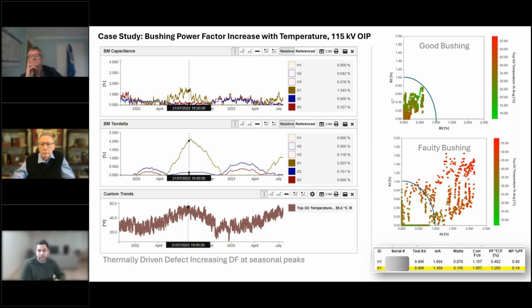Okay. The graphs on the right side actually plot on the vertical axis the relative change in capacitance, and on the horizontal, the power factor. And you can see quite evidently the difference between a good bushing and a bad bushing here, right? So these correlations with operating conditions are very important for identifying certain types of defects. And it's an example here of data and leveraging analytics to detect a very specific defect type that you might not detect well in regular maintenance testing, like the offline power factor test.